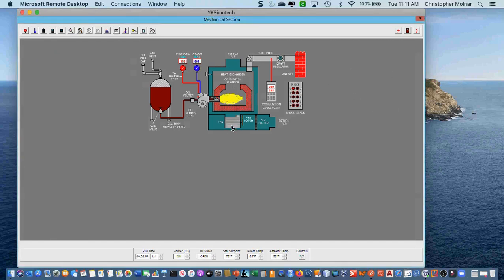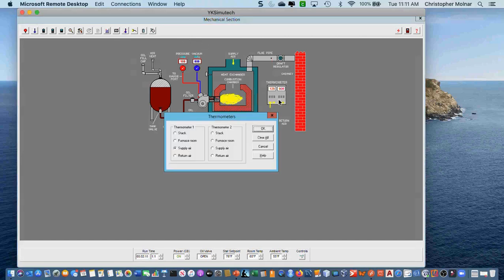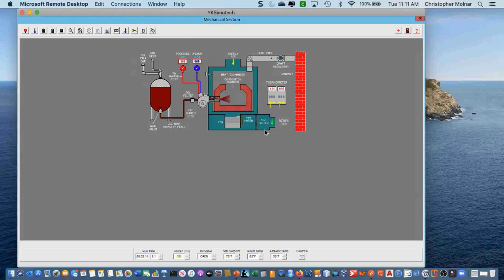Now the fan has started blowing. You can actually see the squirrel cage move. So if I wanted to take a temperature, I could take a temperature of my supply. I could take a temperature of my return. And I can see my supply air is 132, 133 degrees. My return is a pleasant 65. So we're heating the air by that much.